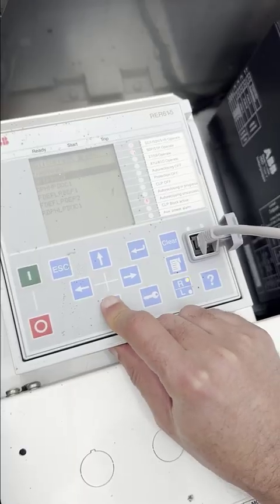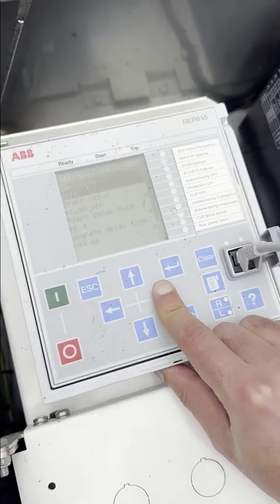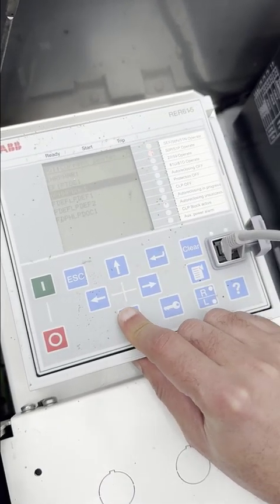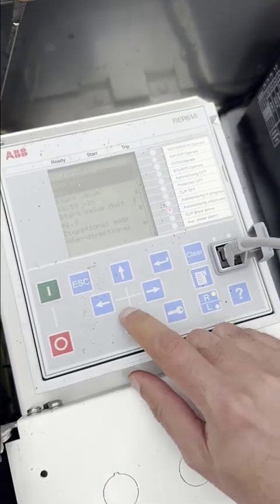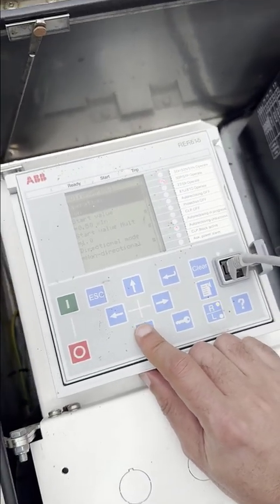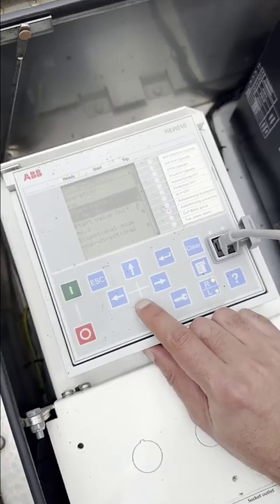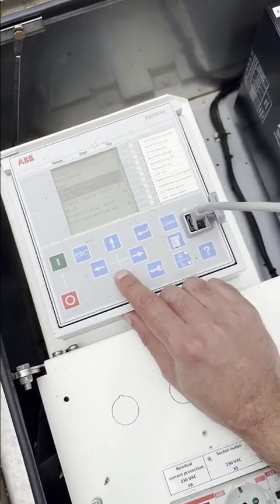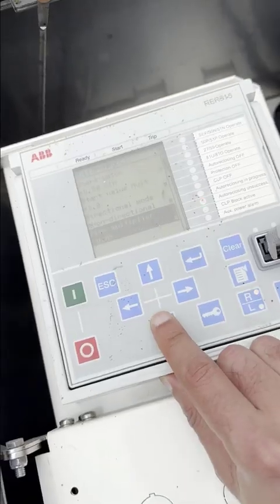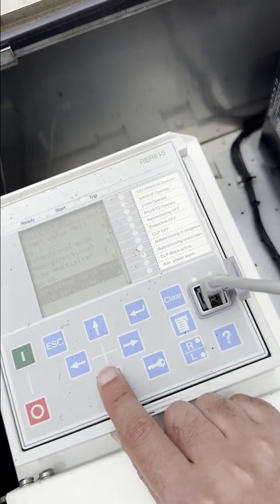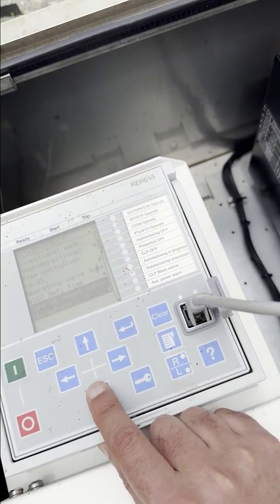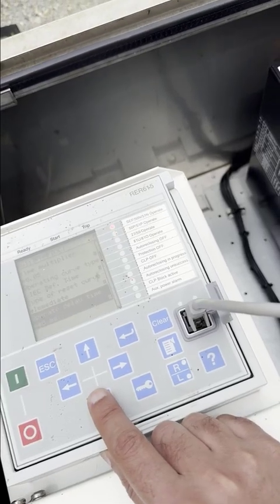So you can enter, then you go for the current protection. We will have here the earth fault PTOC, it's already off. Then we have the instantaneous stage of the overcurrent, as you can see, stage 2. So it's on, and 0.5 multiplied by IN, which means 300 ampere. Then it's non-directional, and the IEC definite time is the curve type, and the operate delay time is 40 milliseconds.